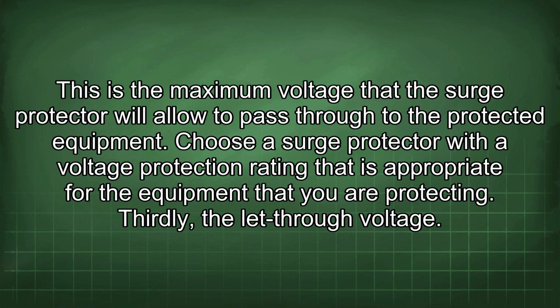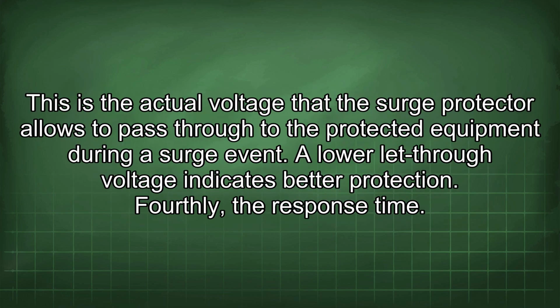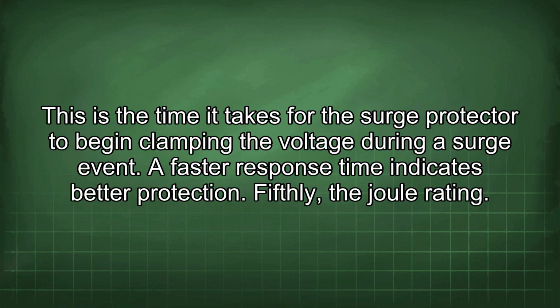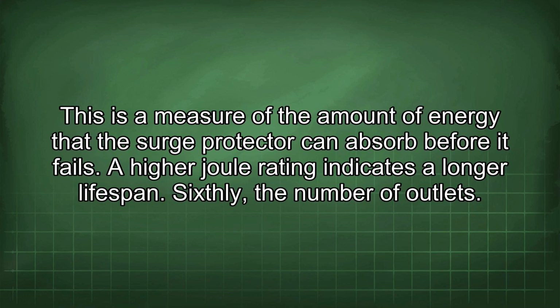Thirdly, the let-through voltage. This is the actual voltage that the surge protector allows to pass through to the protected equipment during a surge event. A low let-through voltage indicates better protection. Fourthly, the response time. This is the time it takes for the surge protector to begin clamping the voltage during a surge event. A faster response time indicates better protection. Fifthly, the joule rating. This is a measure of the amount of energy that the surge protector can absorb before it fails. A high joule rating indicates a longer lifespan.